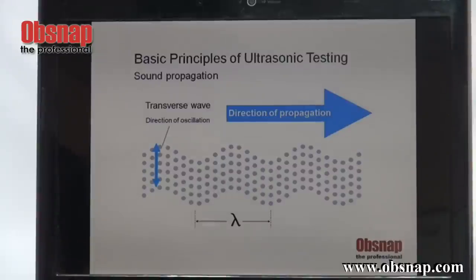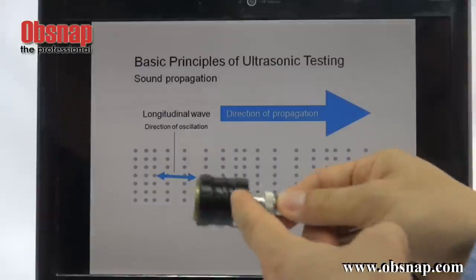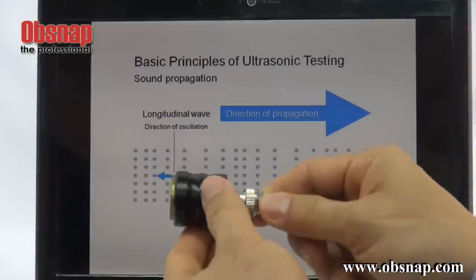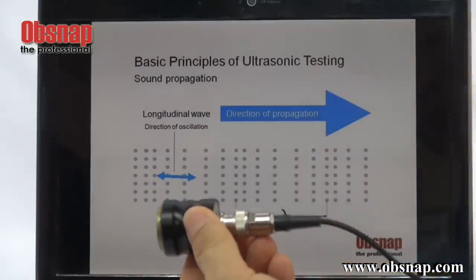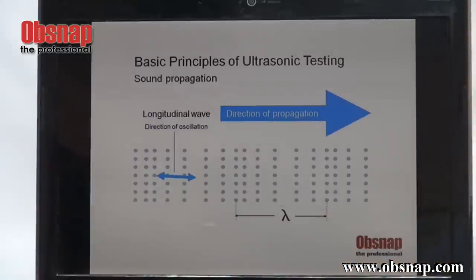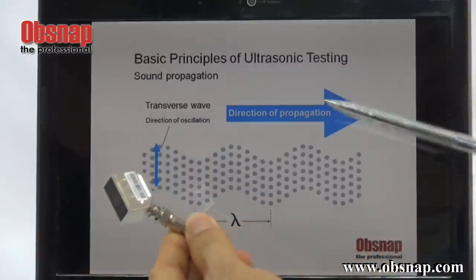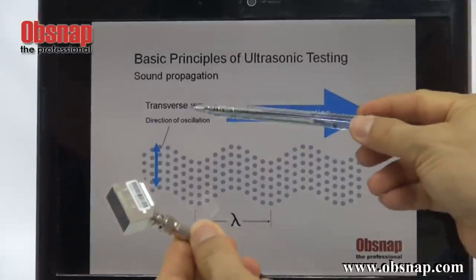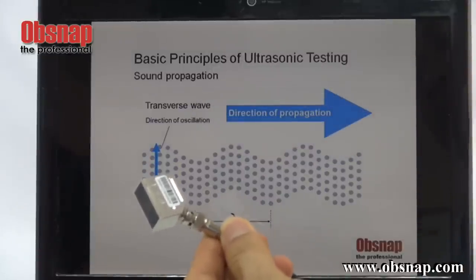What is actually important is that when we use a straight probe, we need to set the frequency to a longitudinal wave — only then can we get an accurate result. And when we are using an angle probe, we need to use transverse wave. Otherwise, the reading is going to be inaccurate.